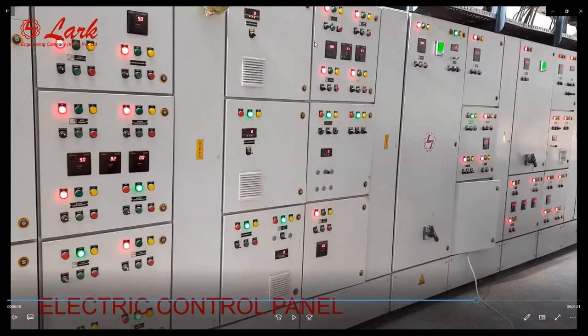And one thing more, even in the existing field mills, we can install separate energy meters for the pelleting and the grinding section. As we are well aware, the ideal power consumption of a poultry feed mill would be around 24 to 25 units per ton, excluding the boiler and the office and other loads.